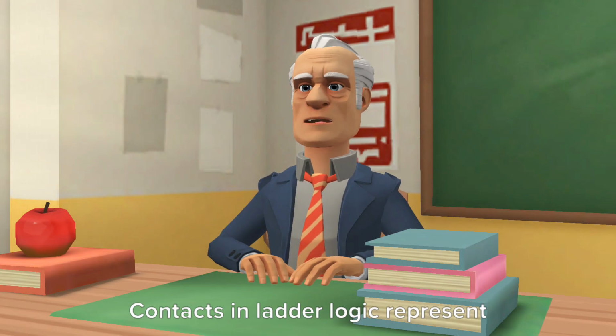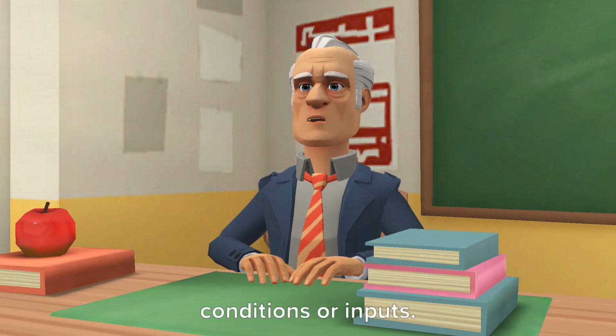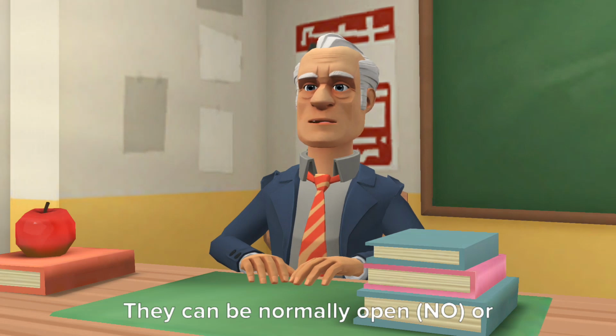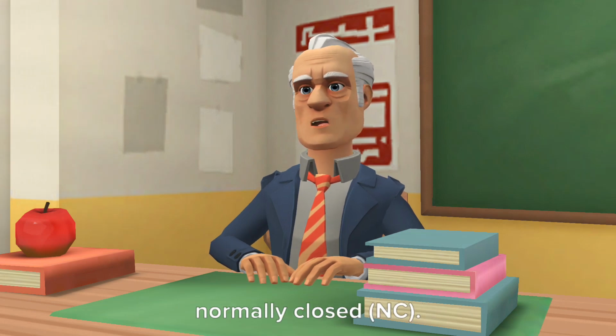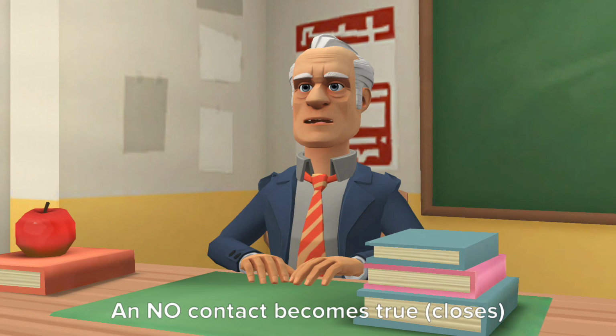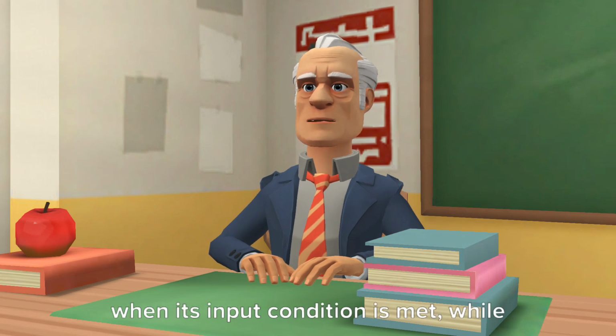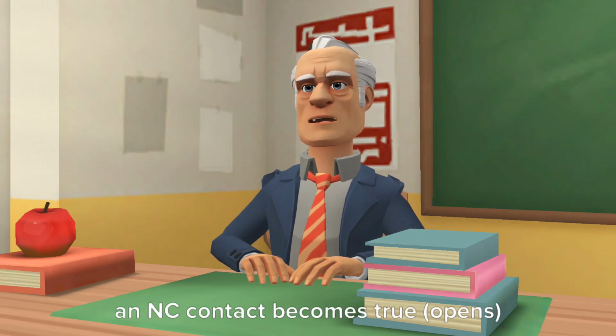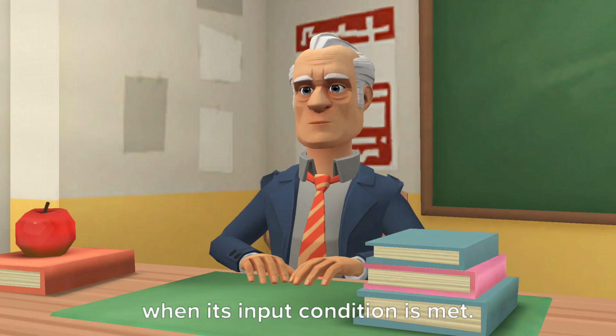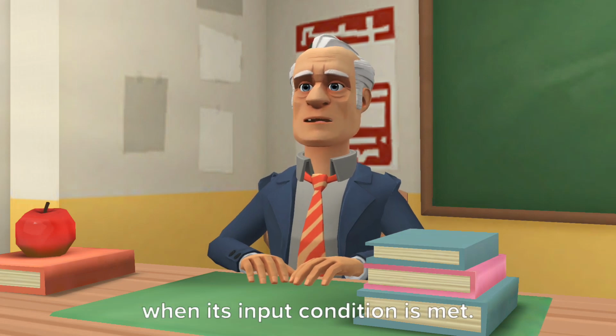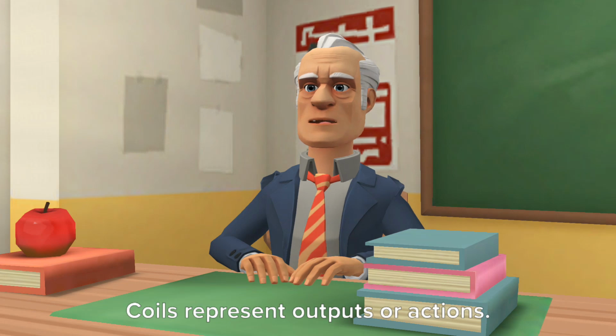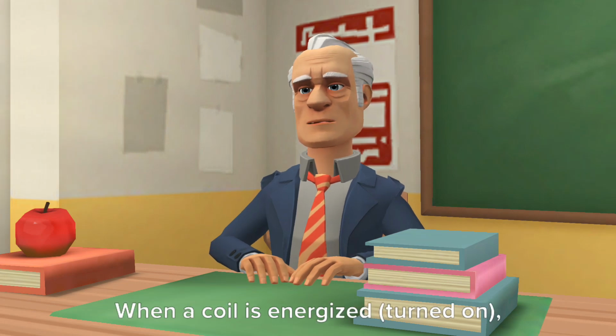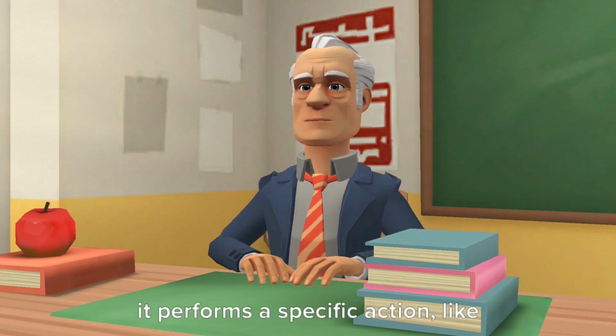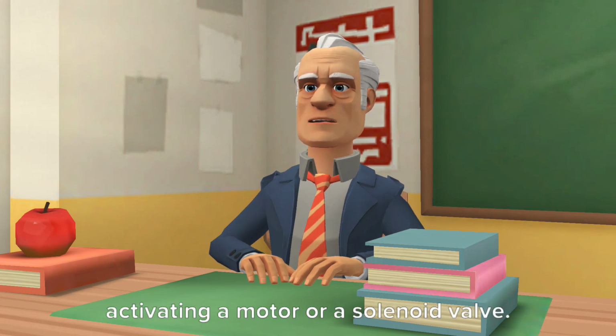Contacts, NO/NC. Contacts in ladder logic represent conditions or inputs. They can be normally open, NO, or normally closed, NC. A NO contact becomes true, closes, when its input condition is met, while an NC contact becomes false, opens, when its input condition is met. Coils. Coils represent outputs or actions. When a coil is energized, turned on, it performs a specific action, like activating a motor or a solenoid valve.